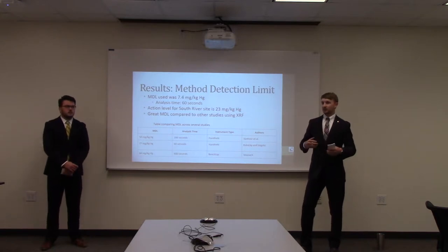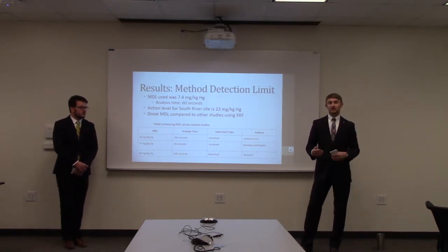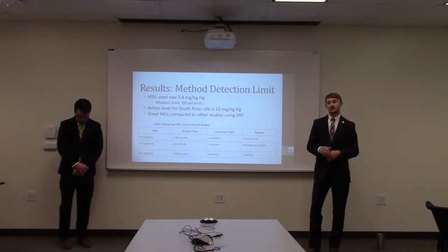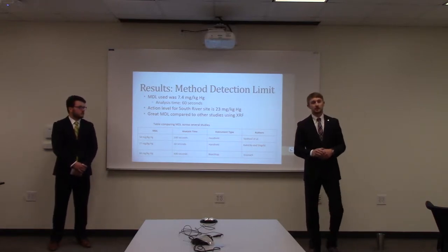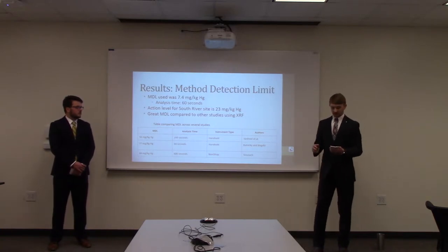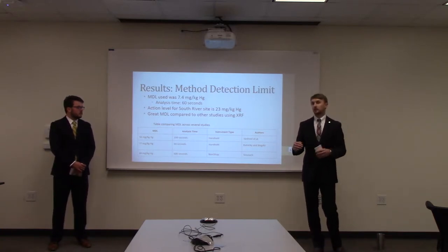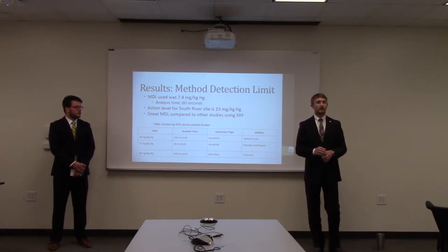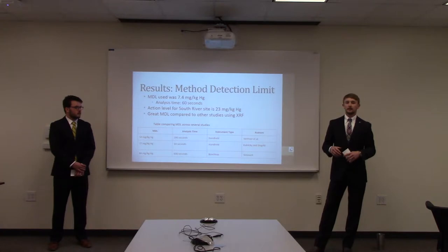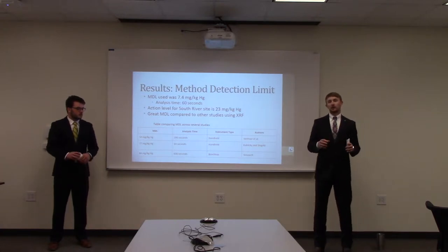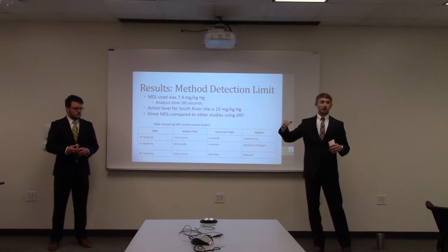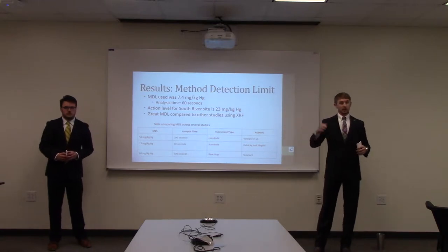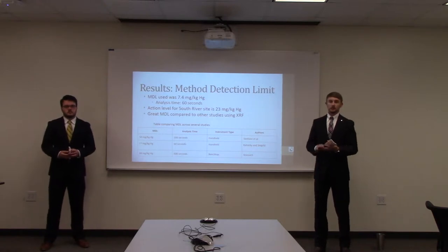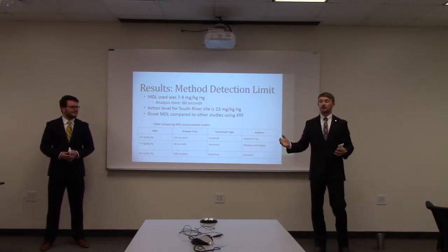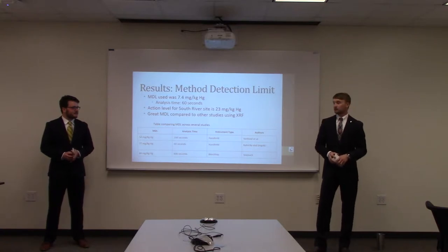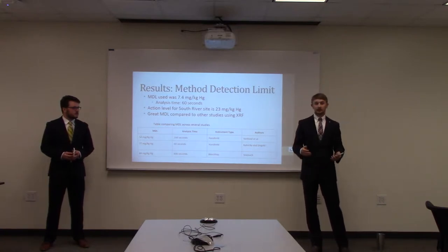We did several different trials on which method detection limit we thought would work best, and we found that a 60-second analysis time gave us a method detection limit of 7.4 milligrams per kilogram. That's a very significant number, because the action level for mercury remediation on the South River is 23 milligrams per kilogram. An action level is the amount of mercury above which remediation is required — above this level, fish consumption advisories ensue and the site needs to be remediated. So our method detection limit is well below that action level, which is good for us and shows we had a great method detection limit.